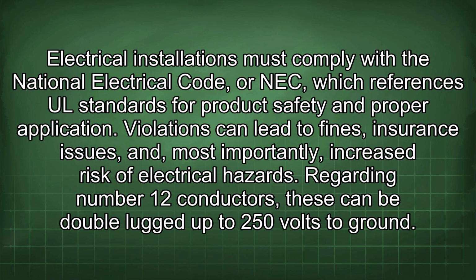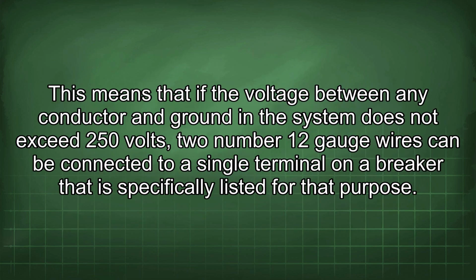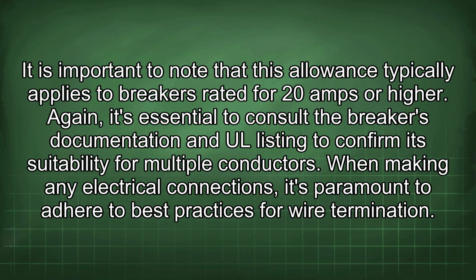Regarding number 12 conductors, these can be double lugged up to 250 volts to ground. This means that if the voltage between any conductor and ground in this system does not exceed 250 volts, two number 12 gauge wires can be connected to a single terminal on a breaker that is specifically listed for that purpose. It is important to note that this allowance typically applies to breakers rated for 20 amps or higher. Again, it's essential to consult the breaker's documentation and UL listing to confirm its suitability for multiple conductors.